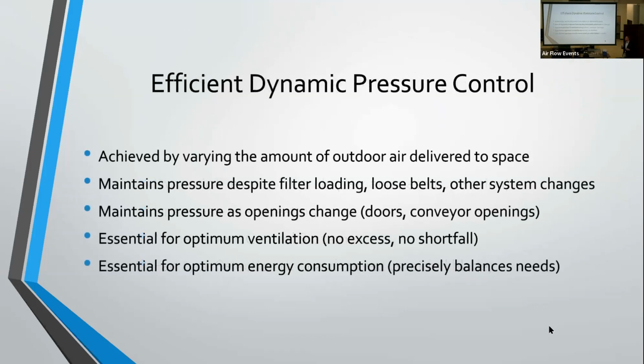Go ahead. What exactly are we talking about there? What kind of pressures are we looking at? Does anybody know what kind of approximate pressure you're looking at for a space to achieve a positive pressure in the building? I know for isolation room control, that's like 0.01 inches, but it used to be like 0.001 inches. Yeah, exactly. Is that ballpark? Yep. I'm surprised it's not higher in an isolation room actually, just compared to, I think in Europe it's 0.1, but you can move the wall at 0.1. That would be extreme, but usually for the applications we see, usually 0.1 to 0.02 is about the most you'll see.